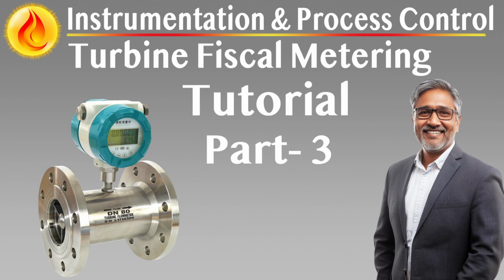depressurizing the system. A second thermowell must be installed adjacent to the primary, positioned on a different radial axis to avoid vortex-induced fatigue. This secondary well enables on-site verification using a high-accuracy reference thermometer. All thermowells must be constructed from corrosion-resistant material, with a minimum internal bore of 6.5 millimeters to accommodate precision mercury in glass thermometers or certified electronic probes. If specified, the manufacturer must supply 2 certified reference thermometers with an accuracy of better than 0.1 degrees Celsius for calibration and verification purposes.